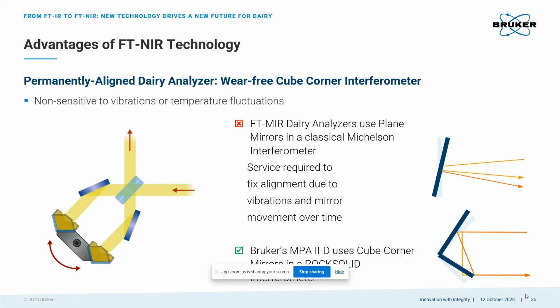Moreover, the instrument maintains the wavelength accuracy over time, and that's our precondition for successful calibration transfer. And because of the cube corner design, we don't have any yearly preventive maintenance or service required in order to align these instrument optics. So our analyzers are designed to be easily maintained by the user, and again, to minimize downtime and minimize your maintenance costs.